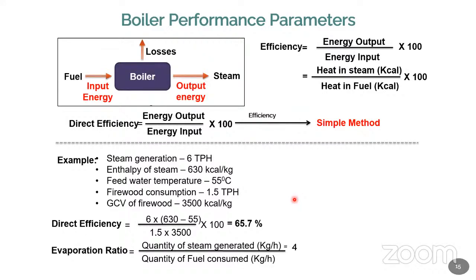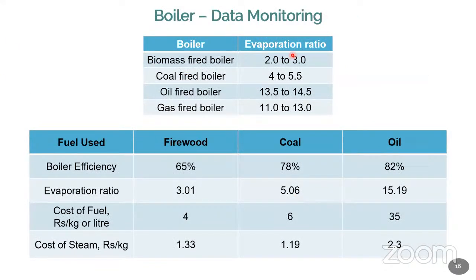So from an efficiency point of view, people go for ER. Evaporation ratio is one of the parameters. Now evaporation ratio can be easily found out by a simple formula: the quantity of steam produced divided by the quantity of fuel. Very simple measurement. You can calculate the evaporation ratio. This ER value is different for different types of boilers. If it's a biomass fired boiler, the evaporation ratio is between 2 to 3. If it is a coal fired boiler, it is between 4 to 5.5. If it's an oil fired boiler, it is between 13.5 to 14.5. If it's a gas fired boiler, it is 11 to 13.